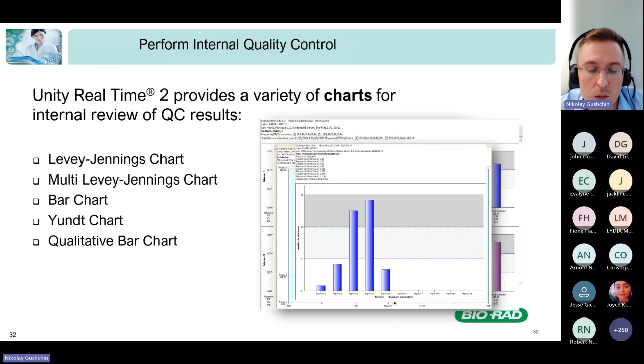And just to show you an example of how this can be used, I want to show you a real lab case which was published in an article. Here we have two Levey-Jennings charts for triglycerides. The chart on the top shows level 1 and level 2 for the triglycerides, and the chart on the bottom shows the electrical conductivity of the water source used for this instrument. The lab also recorded all events happening in the lab, like water filter maintenance, instrument maintenance, and so on.